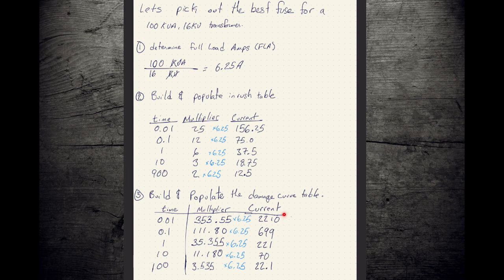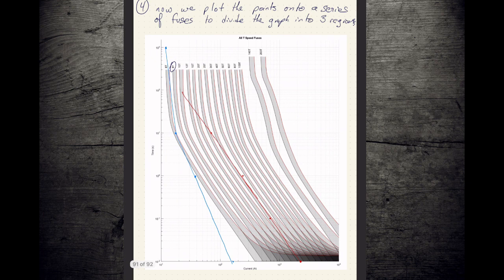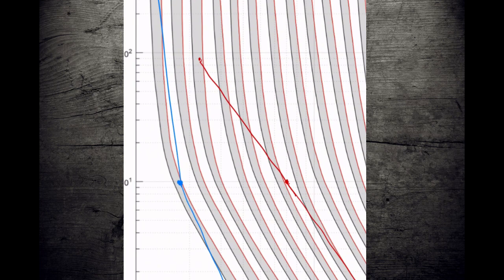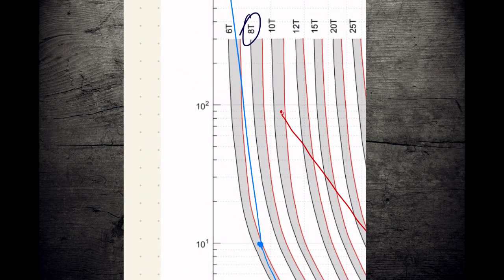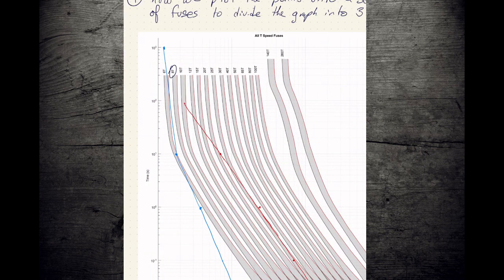Now we can go back. We can plot our points for our damage curve. This time I did it in red. So we plot our points. And what we see is that some of our fuses, so the 6T, for example, would not be a good candidate fuse. It operates on the left side of the inrush line. So we could be at, for example, 20 seconds, and we could be at 15 amps, and that puts us right about here. And it's very possible that we operate our fuse before we hit our boundary. So we could have an inrush condition that put us right here and our fuse tripped.